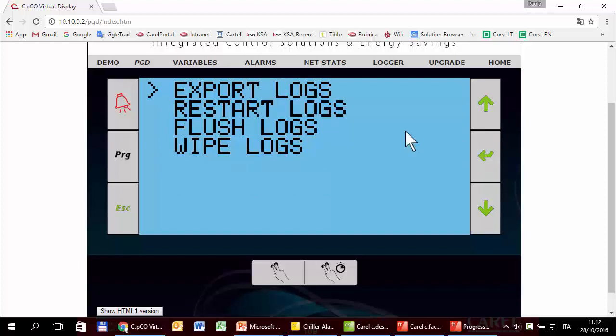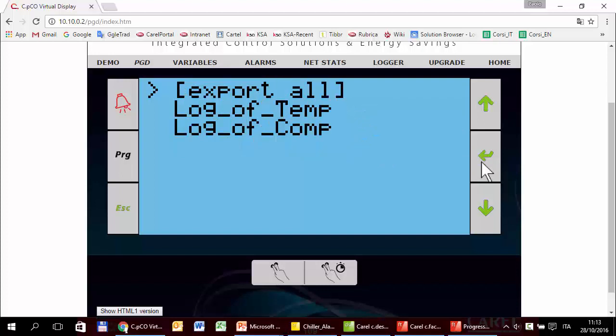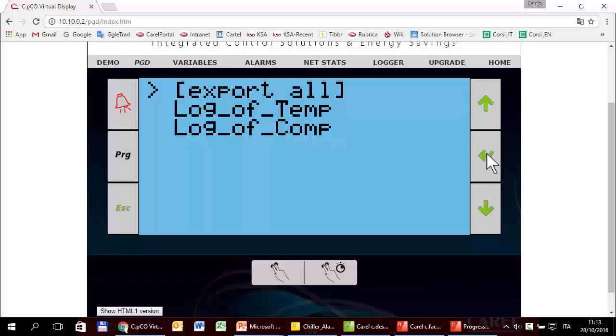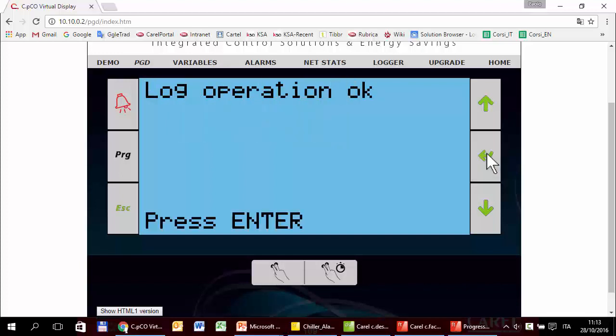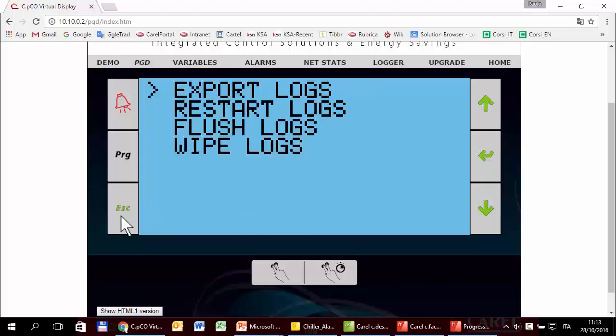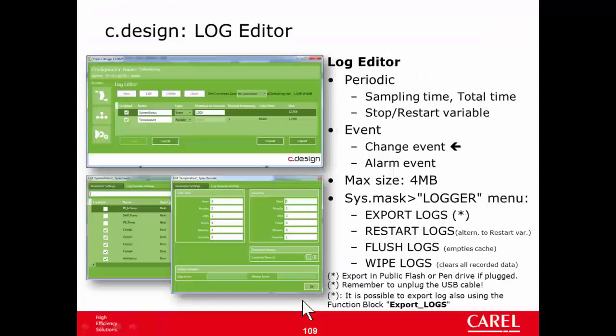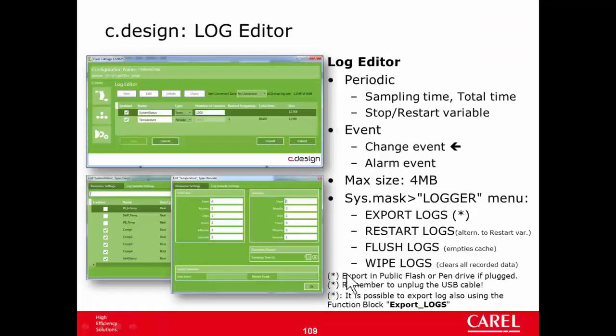We can export and other options. Now we can export. Here are the two logs that we have configured. We can also export all. And export. Log operation. Press enter. The point is, where are the files? As usual, it is written. The export logs exports in the public flash memory or the pendrive if plugged.